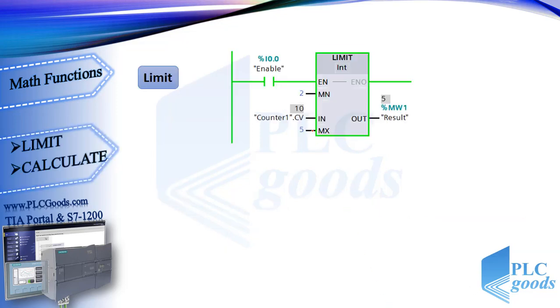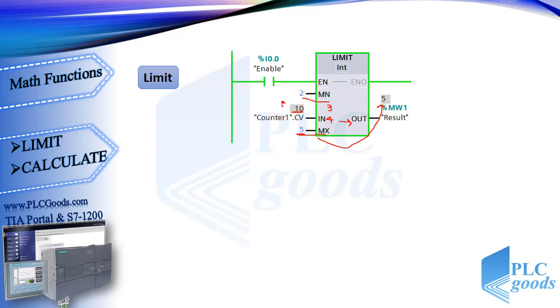The next instruction is LIMIT, used to limit the value at input IN to the values at inputs MN and MX. If the value at the IN input is between MN and MX, it will be copied to the output. For example, if the counter value is 2, 3, 4, or 5 it is copied to the output. But now it is 10, which is greater than MX, so instead of 10 we'll have 5 at the output. If I reset my counter to 0, which is less than 2, the output of this function will be 2.